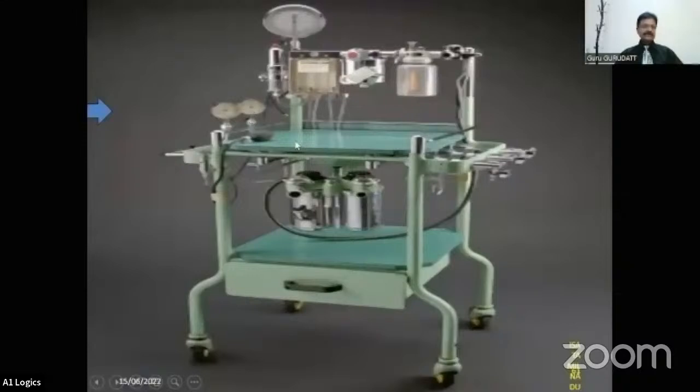In the older machines, there were no pressure gauges for nitrous oxide. There were only pressure gauges for the oxygen. The basic thinking in those days was that nitrous oxide is a liquid gas, and whatever pressure is shown in the pressure gauge is the vapor pressure. Until the last drop of nitrous oxide is vaporized, the pressure gauge will not show any change in the pressure, because it is continuously the vapor pressure that is being shown. That is why, in the older machines, you may be asked why there is no pressure gauge for nitrous oxide.